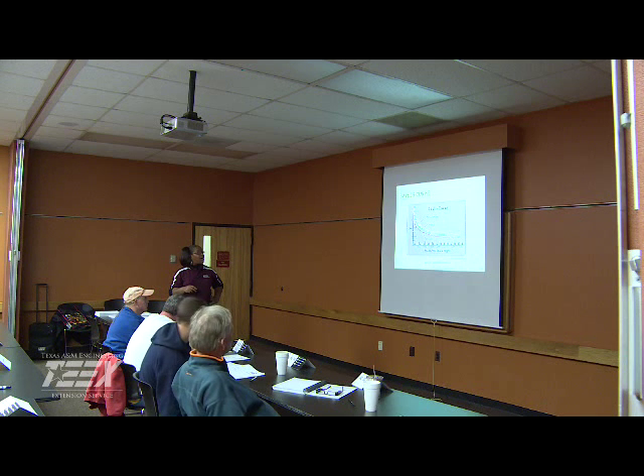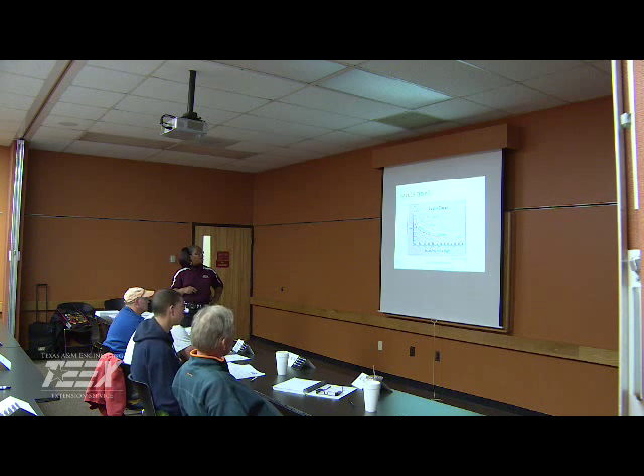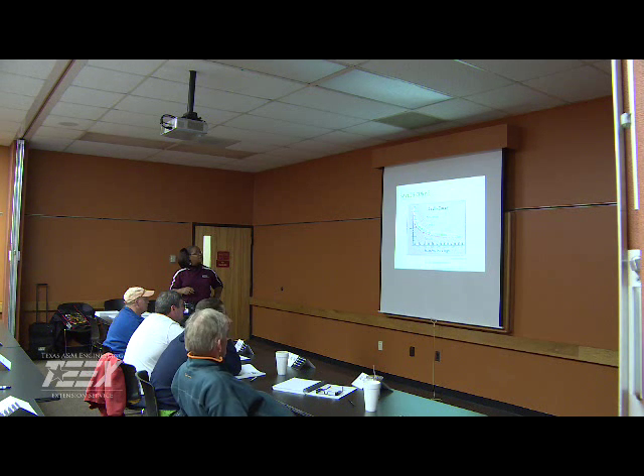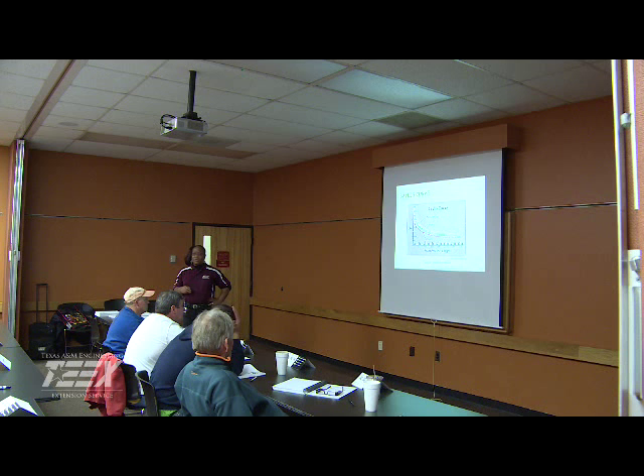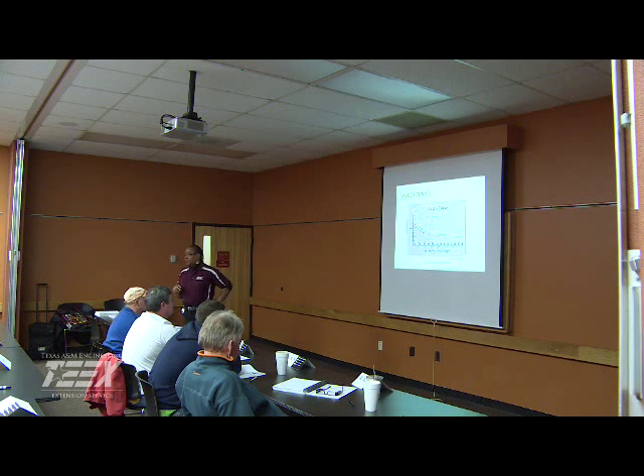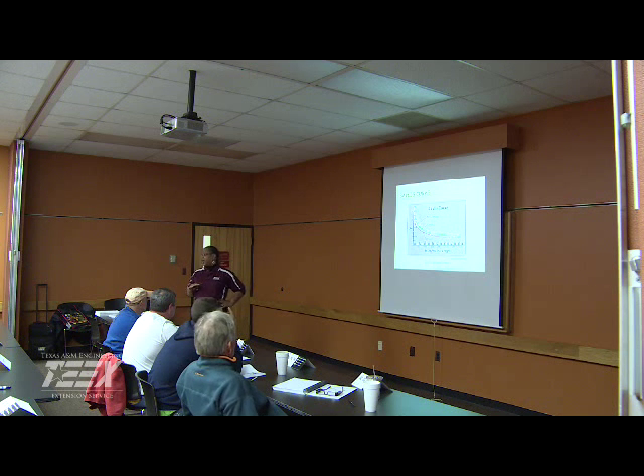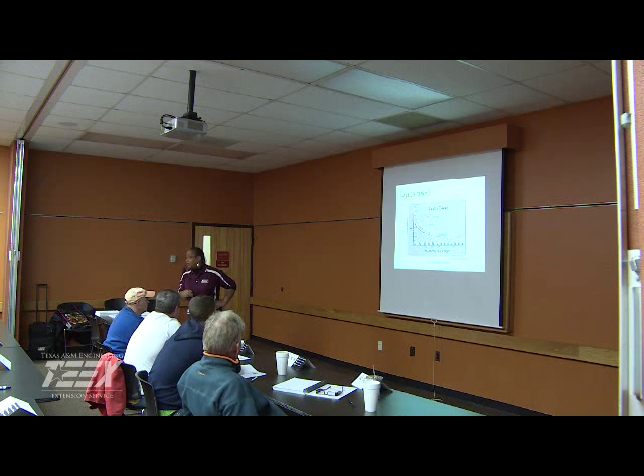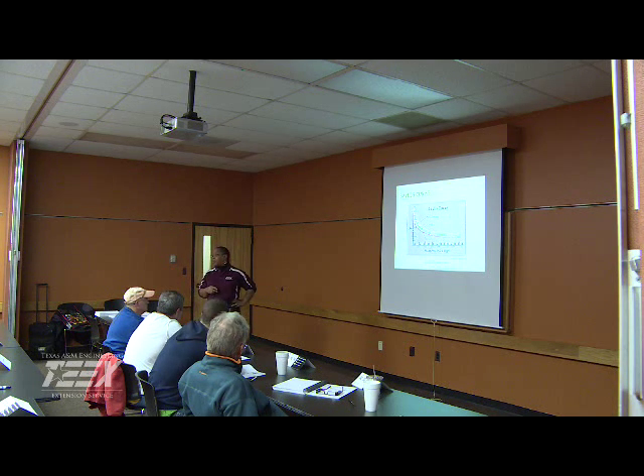So based on that plot, let's say my pH is 7, which is where we want it to be, and my alkalinity is about 200, then that's about where I want to be. I want to be in that area there. So 200 or better alkalinity around 7. You're talking like that without adding any chemicals? Yeah, this is just without adding chemicals. Of course, as you add lime or soda ash or what have you to increase that pH, it will affect where you fall. So you can manipulate to be in the right area by the addition of chemicals also.